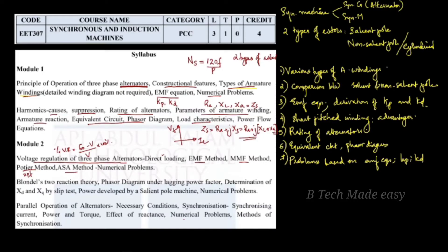The next method is called the ZPF or Potier method. If you are using this method, you can use the OCC (open circuit characteristic) and the effective armature resistance. This method uses the zero-power-factor condition to find the Potier reactance.